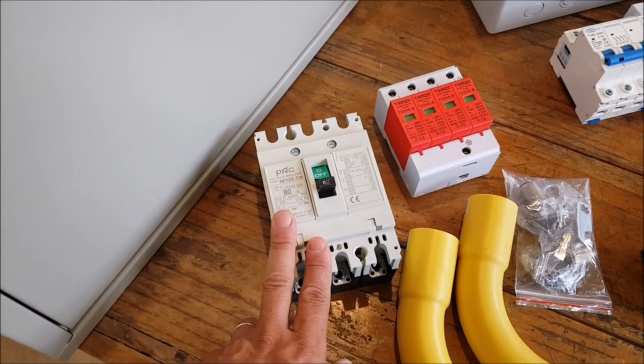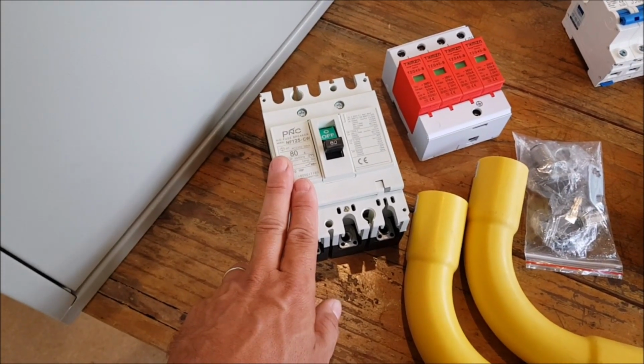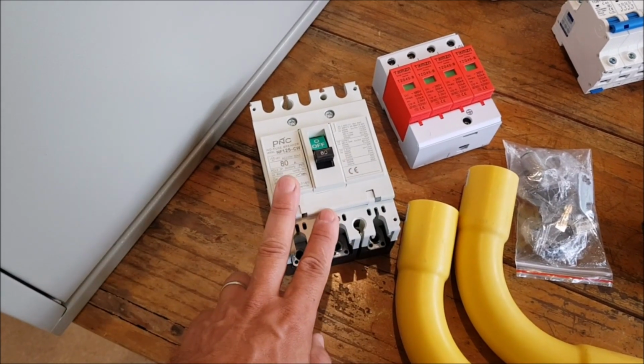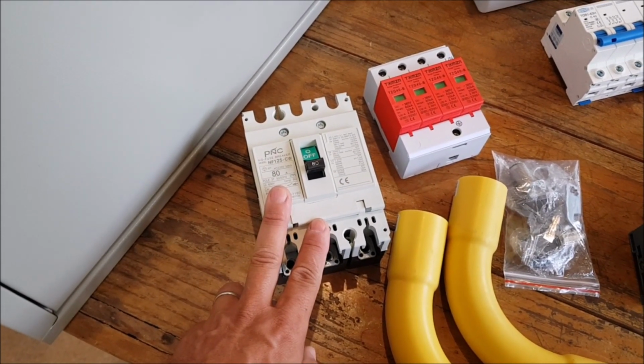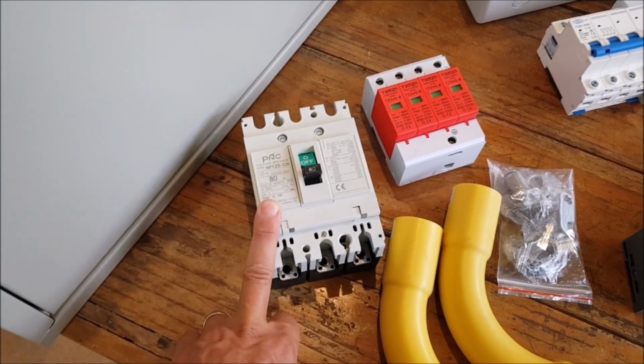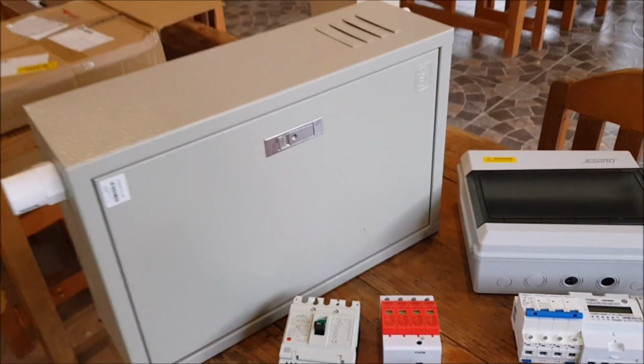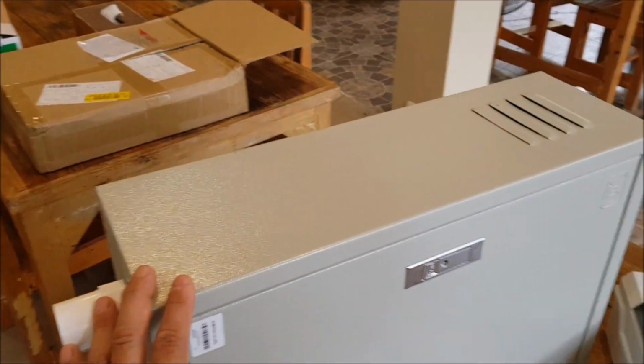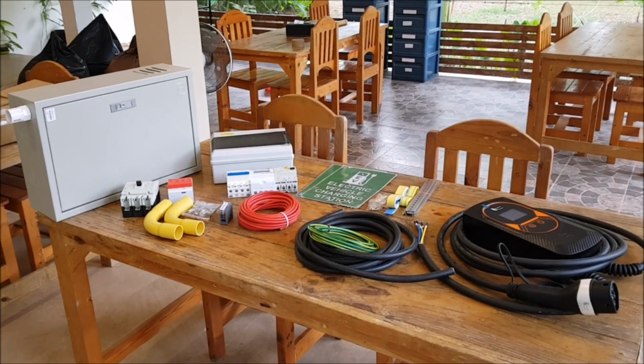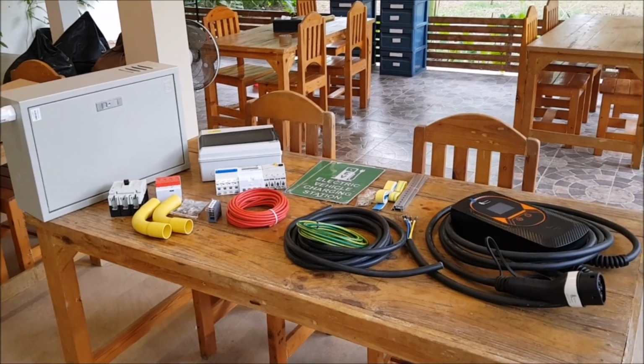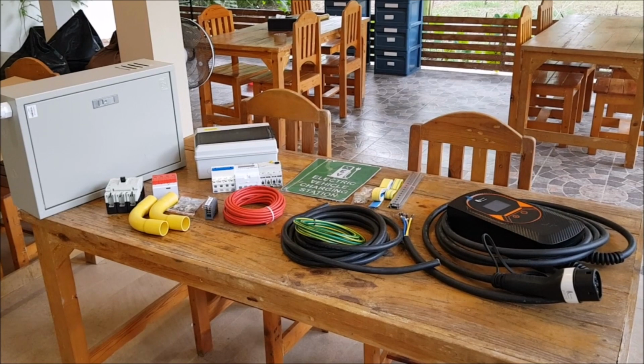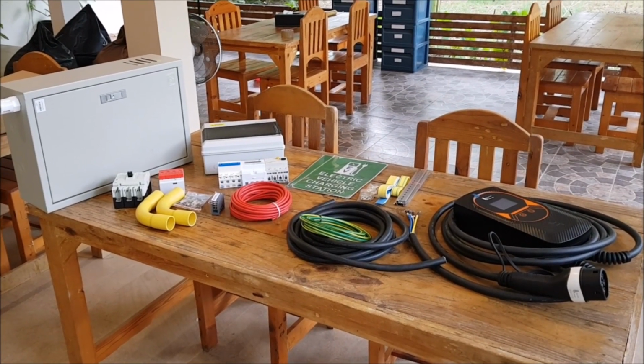A new main circuit breaker for inside the MDB. I want to change the 3-phase circuit breaker which is there from 100 amps to 80 amps. Why exactly that is, I will explain to you later. Then in this cabinet, all the cables will kind of come together, go to the other places, and also the charging cable will be stored. Okay, that's about it. So we're going outside to the place where this will all be installed, and then just start with the work.